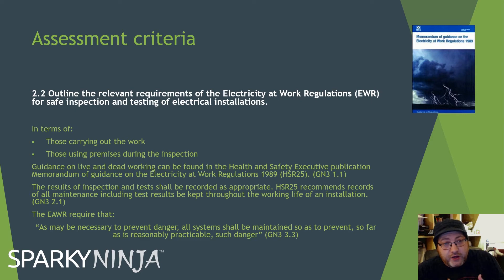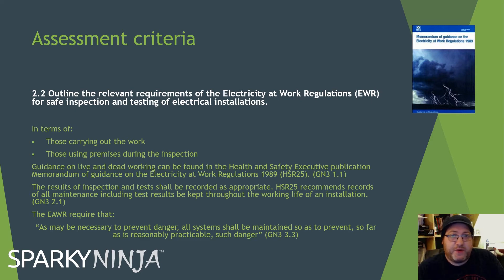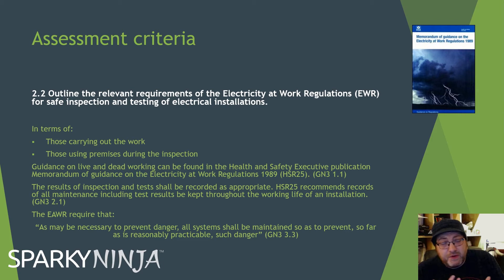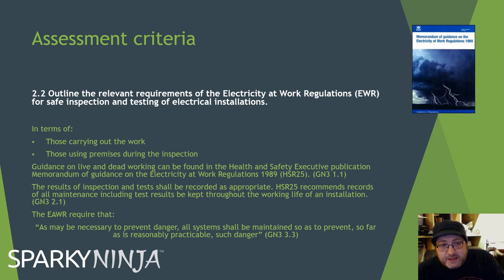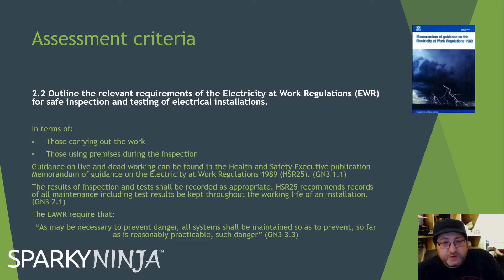This is a key point with the pre-site survey. If you visit a factory at one shift pattern and then send electricians in for specialist testing on a different day with a different quantity of staff or method of work on site, you've got a problem because the risks haven't been properly assessed. Ensure the working conditions and environmental characteristics of the site are fully understood, including electrical risks and building risks such as shutting down emergency lighting, lifts, and escalators.